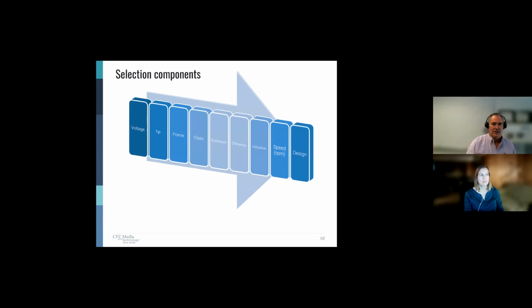There are lots of selection components when we talk about motors. This graphic shows some of them. You know, what is the voltage? What is the horsepower? What's the frame, the class, the enclosure, the efficiency? Are we induction? Are we synchronous? How fast do we want it to run? What motor design type is it? Lots and lots and lots of things that we have to take into account if we're actually selecting a motor.